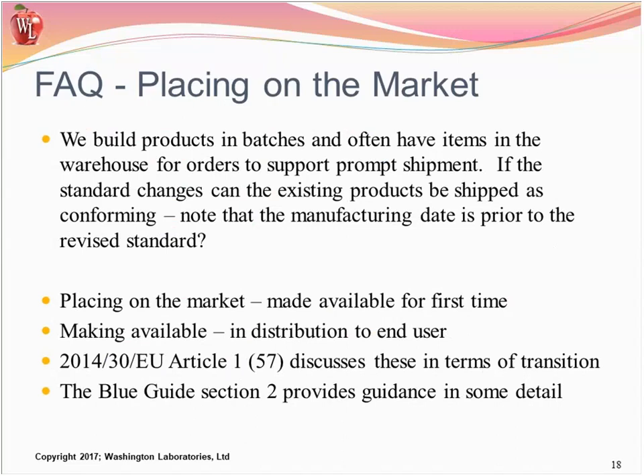I've got a couple of frequently asked questions. We build products in batches and often have items in the warehouse for orders to support prompt shipment. If the standard changes, can the existing products be shipped as conforming? Note that the manufacturing date is prior to the revised standard. It usually comes down to when I am placing it on the market—that's the first time. Making available is when it's in distribution. So if I have it in a shipment mode satisfying an order, then it can be shipped. Making available is the key area here.